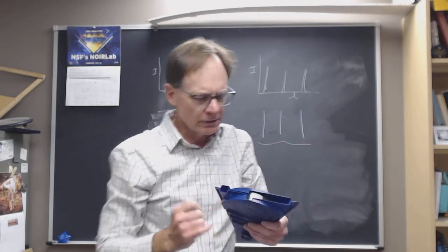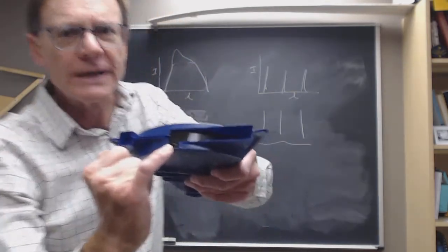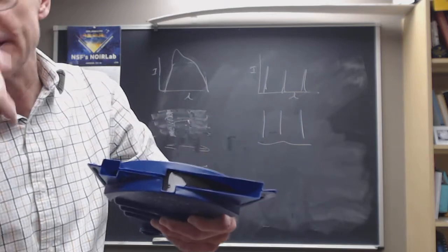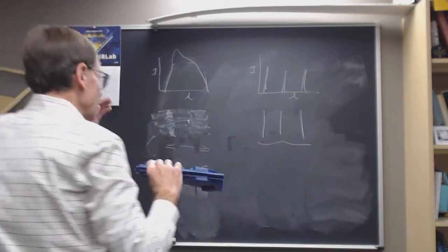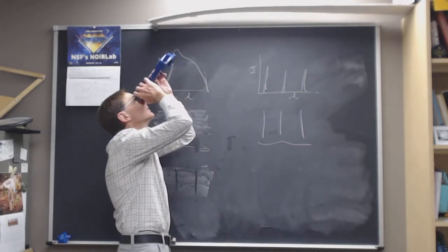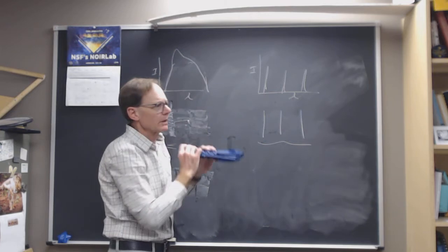And we can either take a pencil or a pen and use that hole that's right there and adjust this back and forth to make it line up, but it moves pretty rapidly, so sometimes it's better just to say, I'm a few nanometers off, and I'm just going to subtract or add that few nanometers to my measurements. So we can do that with the fluorescent light.